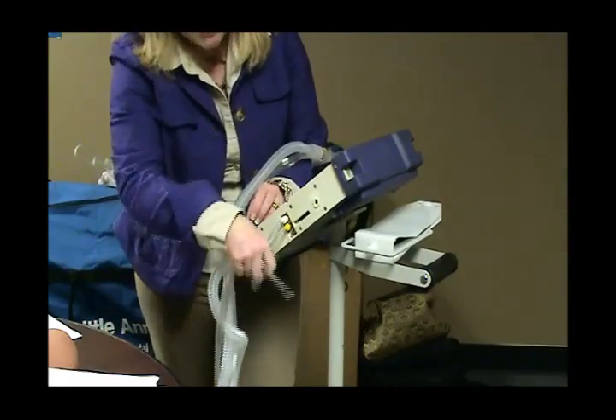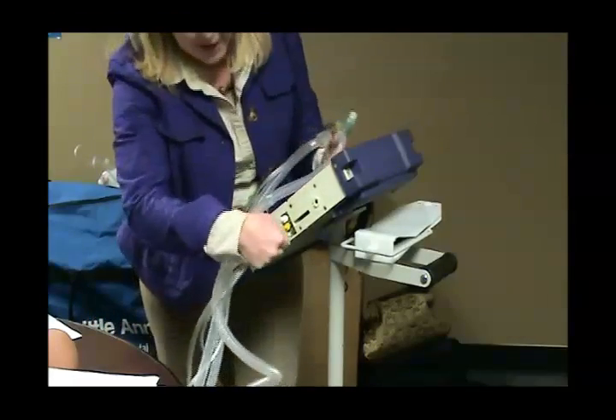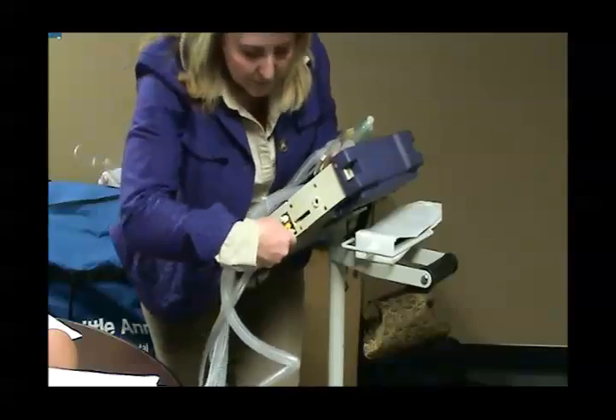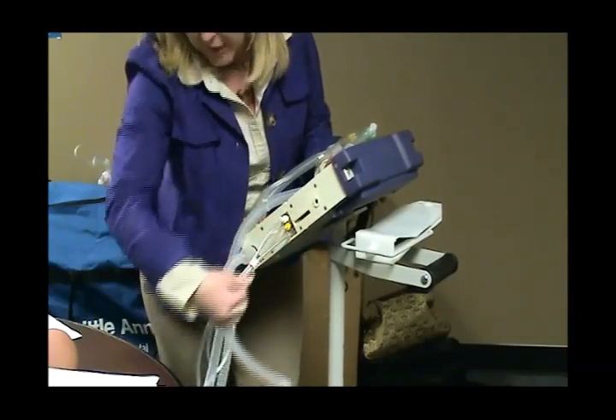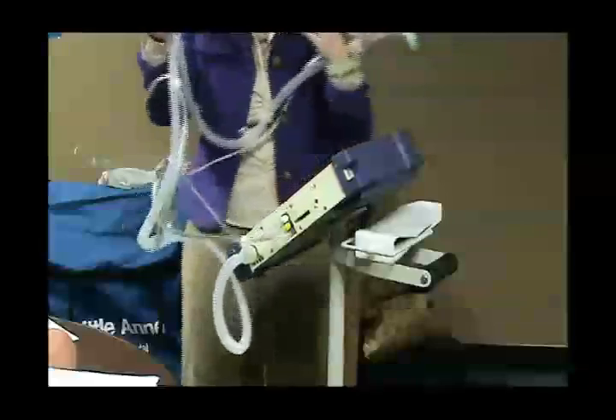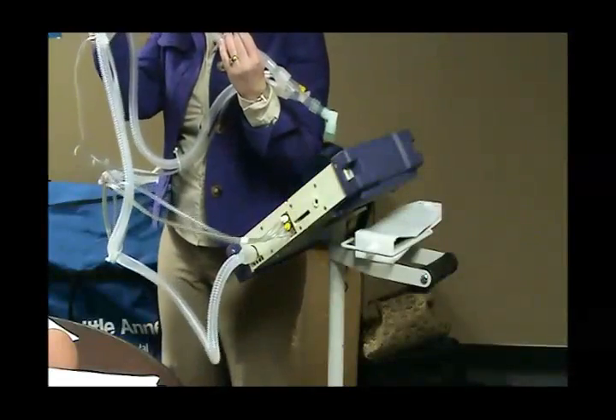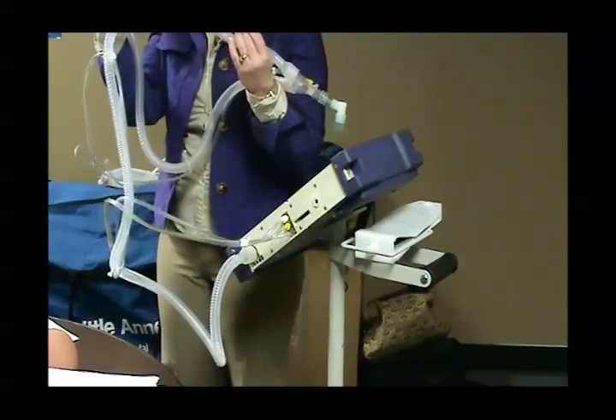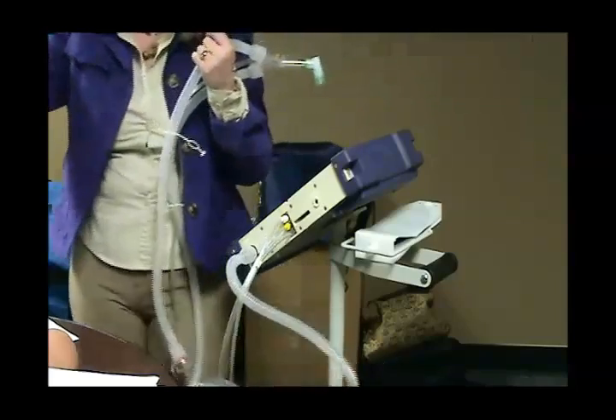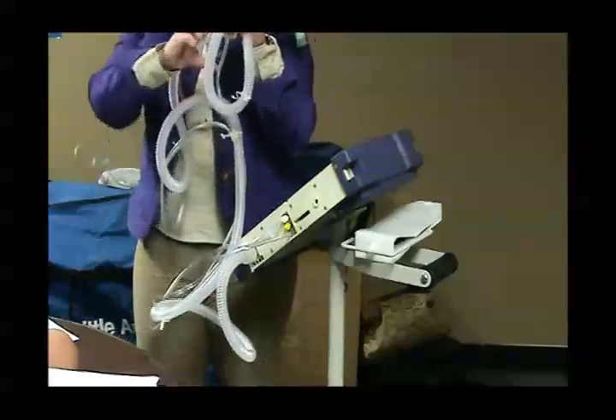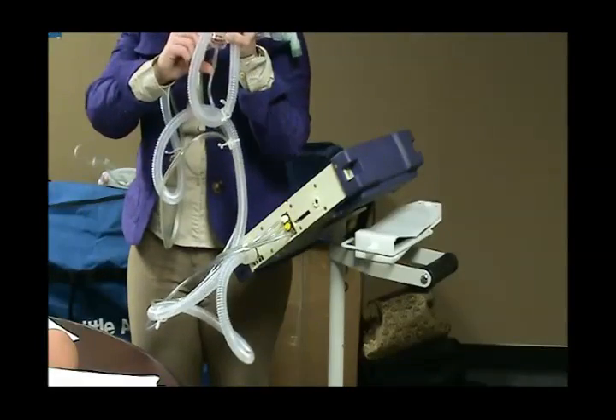Okay? The last one is your exhalation valve. It's the only hole left, and it presses straight on. If I trace it back, it goes to my exhalation valve. Okay? This is where my patient's exhaled air comes out. All right? So on your one with your PEEP valve, you've still got your external exhalation valve, but then you also have a PEEP valve on there.